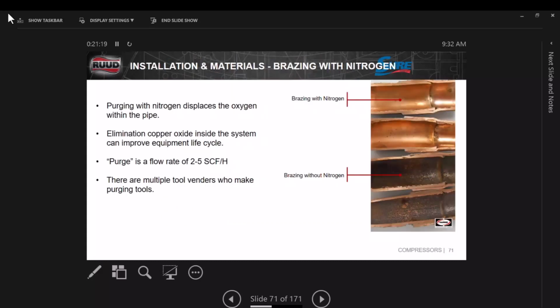I haven't had a TXV failure or a compressor failure since I started. Congratulations. That's great. That means that you're doing something right. That doesn't mean that you're not going to ever have one. That happens, right? But on one of my installs, I have not had a compressor or a TXV failure since I started flowing nitrogen. Flowing nitrogen. That's right. There you go. Because this is what we end up with. When we reuse a line set that's had mineral oil in it for 30 years, mineral oil will coat the inside of the line.